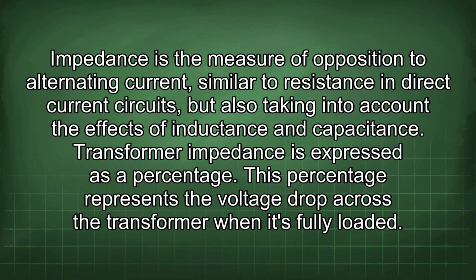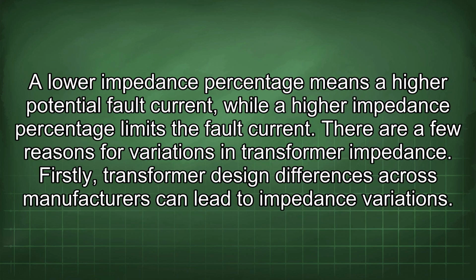Transformer impedance is expressed as a percentage. This percentage represents the voltage drop across the transformer when it is fully loaded. A lower impedance percentage means a higher potential fault current, while a higher impedance percentage limits the fault current.